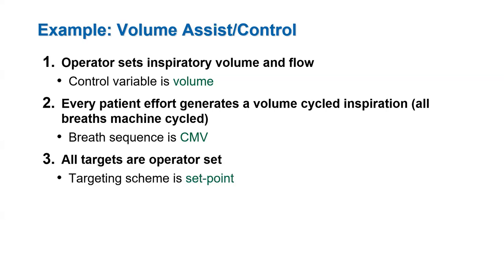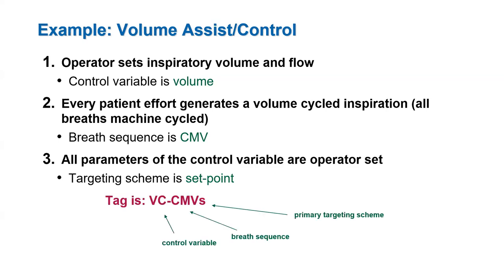For step three, we note that all targets are operator set. There is no automatic control of targets. Hence, the targeting scheme is set point. We will bring all this information together in the mode abbreviation or tag. In this case, VC indicates volume control, CMV indicates continuous mandatory ventilation, and the lowercase s represents set point targeting scheme.